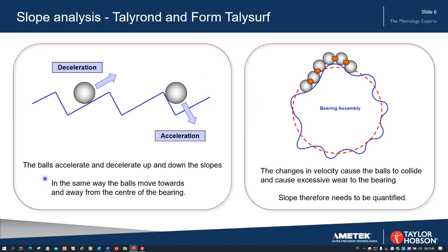That's the same thing that happens on a typical bearing race — the balls will move towards and away from the centre of the bearing. Where we have many more undulations, the many ball bearings in the bearing race will change in velocity and the balls will collide. As they collide they will cause excessive wear to the bearing, so we clearly need to quantify the value of slope.